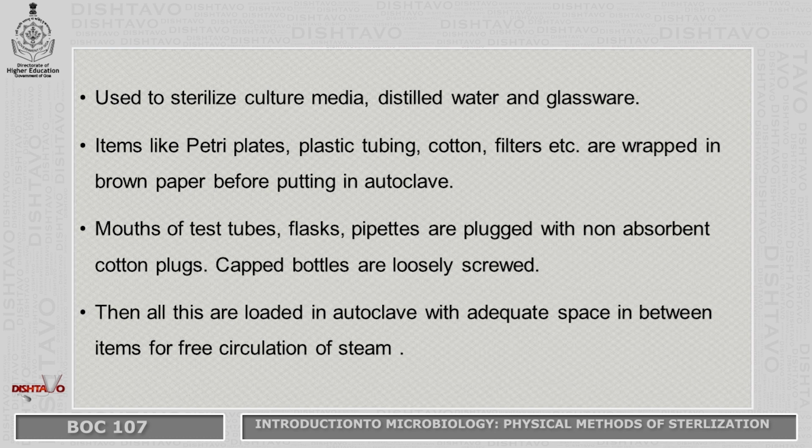The mouth of the test tube, flask, pipette has to be capped or plugged with a non-absorbent cotton plug. Then all these are loaded in an autoclave with adequate space maintained in between the items for free circulation of the steam.